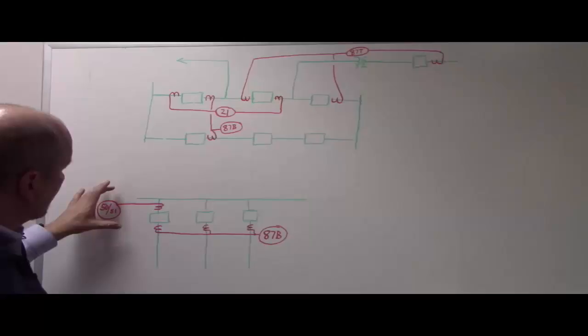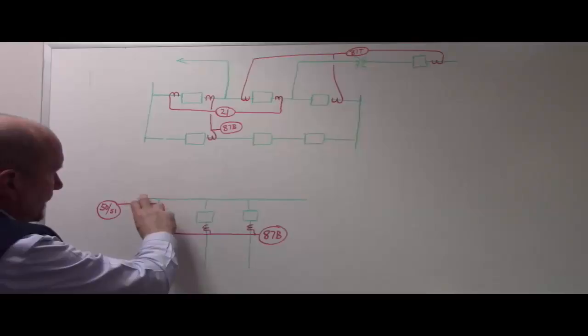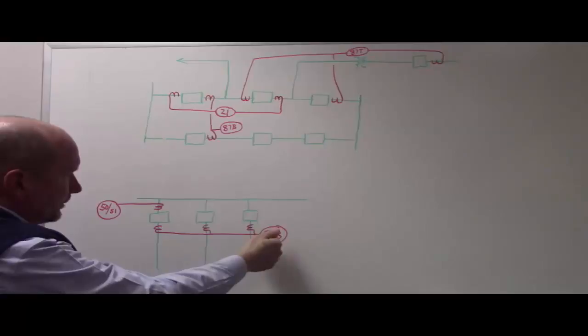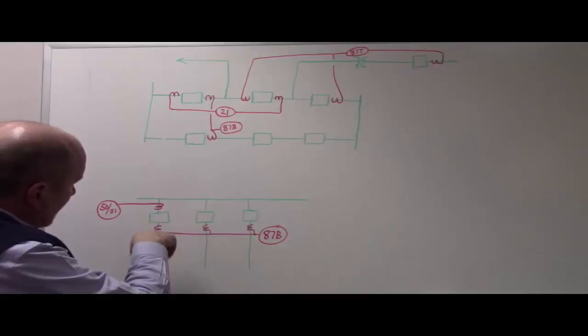In a different configuration — a radial bus scheme — to protect the main bus we put CTs on the far side of each circuit breaker and run them to a bus differential relay. For each one of these breakers, the zone looking outward uses a simple overcurrent relay, a 50/51. If there are any questions on this, it's really important that you get this straight — it is very fundamental to substations.